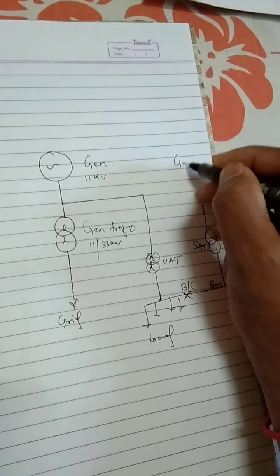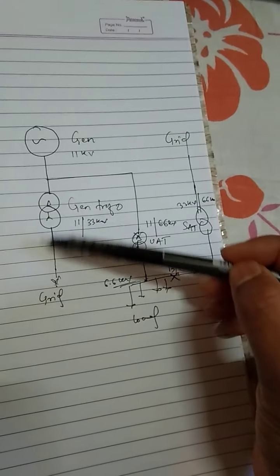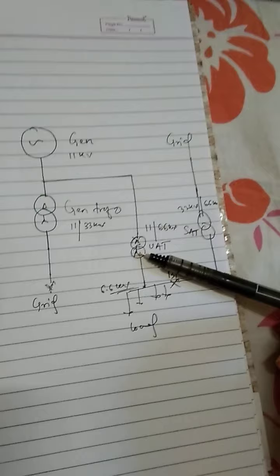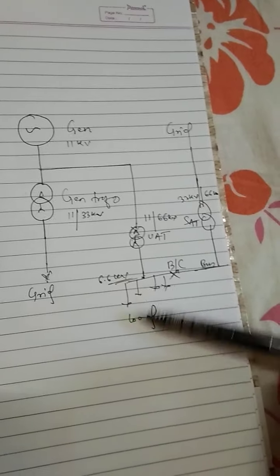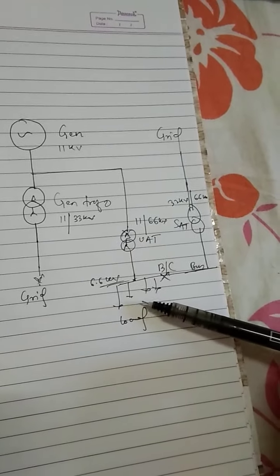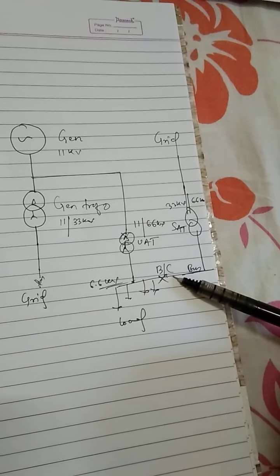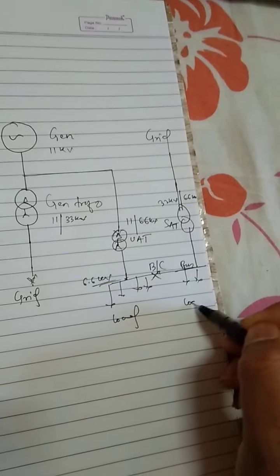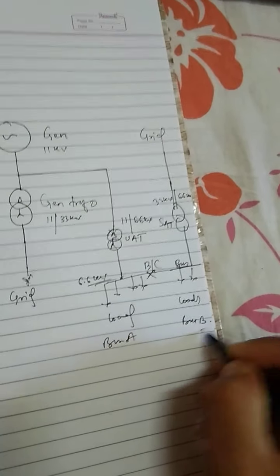if Class A protection acts? As soon as the generator is synchronized with the system, the generator starts supplying power to the grid. At the same time, we have also connected a transformer in parallel. So here a step down transformer is there. We have a bus and it supplies the load. In case our generator trips, it will stop supplying the load. Here is the load. Here is a bus coupler. In this we have also some loads on bus B. This is bus A and bus B.